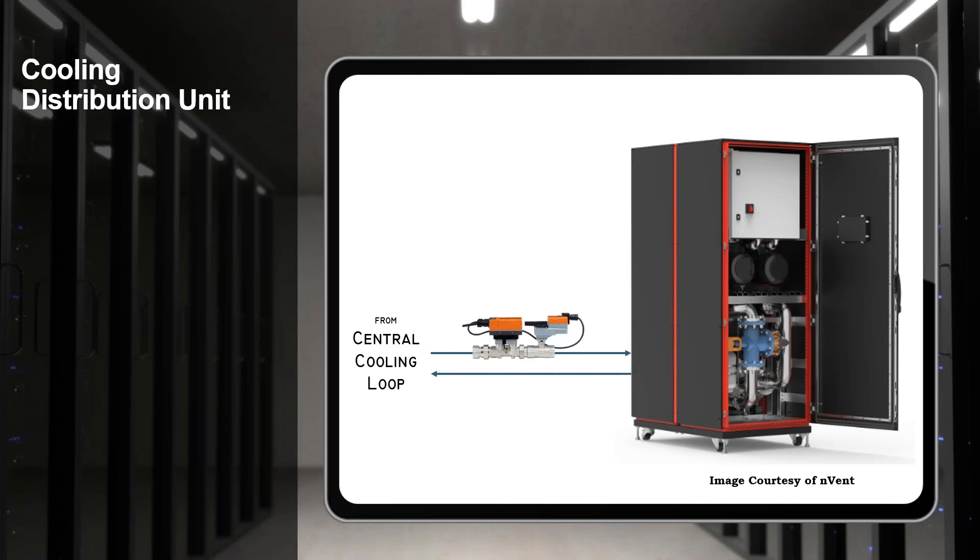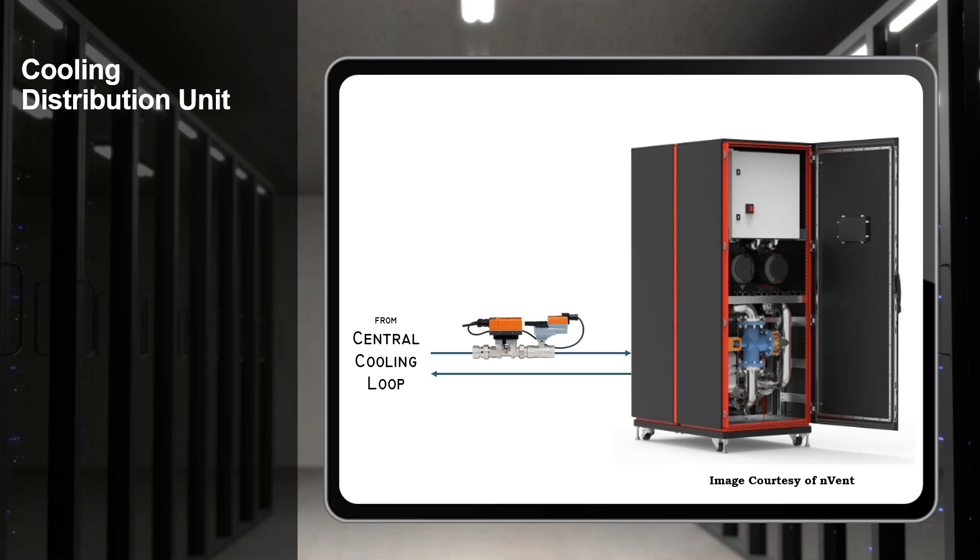Let's talk about equipment that we're going to wind up in space when we adopt liquid cooling solutions. Let's start with a Cooling Distribution Unit or CDU. A CDU is a cabinetized heat exchanger that we're going to put in or near the space. It allows us to take the chilled or cooled water from a central loop and exchange that heat onto the technology side. We're always going to need to control the flow on the central loop side, on the building side of this loop. A pressure independent valve and the EPIV is always a good option here - it allows us to have constant and measurable flow input into that device.